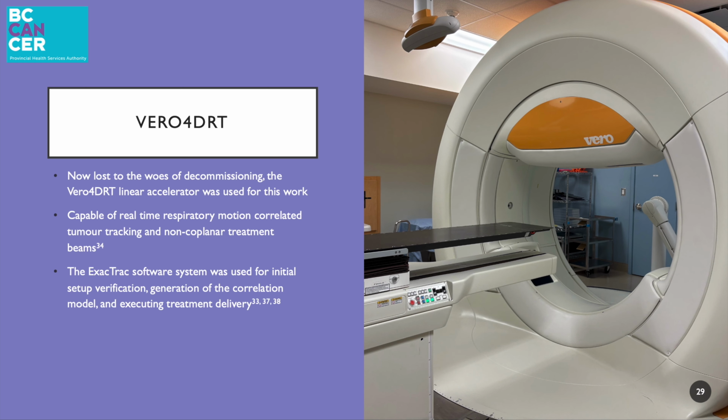Now, the linear accelerator that I used for my work, which has unfortunately since been decommissioned at BC Cancer, is the Vero 4DRT linear accelerator. And here you can see it is an O-ring LINAC, so a bit different than the one I was describing before. Now, this accelerator is particularly cool because it is capable of real-time respiratory motion correlated tumor tracking, as well as non-coplanar treatment beams. It comes with a software system called the ExacTrac software system, which is used for initial setup verification, generation of the correlation model, as well as executing treatment delivery.